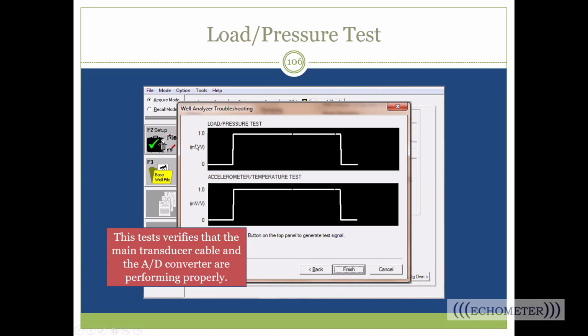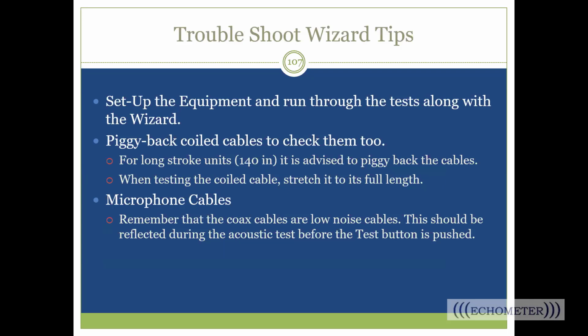If you see one of them start out at that 1 millivolt per volt, if you've got a shorted out cable, or you see no response, then that's an indication that you've got a damaged cable. So this is a way that you can check both of your cables. You can piggyback your coil cables onto that to check your coil cables. Make sure if you do that you stretch that coil cable out. When it's on the well and the well's operating, it's stretching those cables out. You can do that in this cable checker troubleshoot wizard. Again, this isn't in TAM, but it's in TWM, and it's just a good way for you to check your cables.